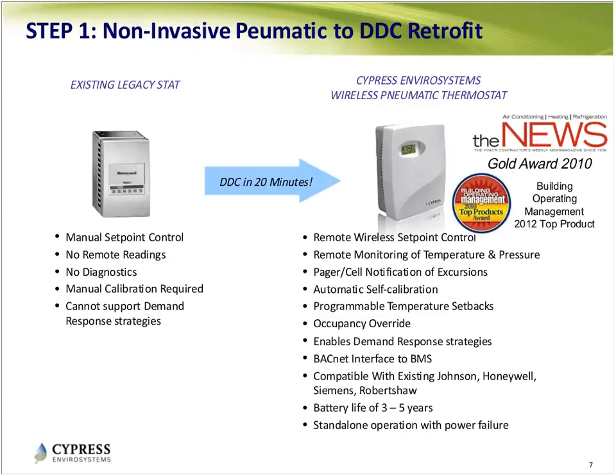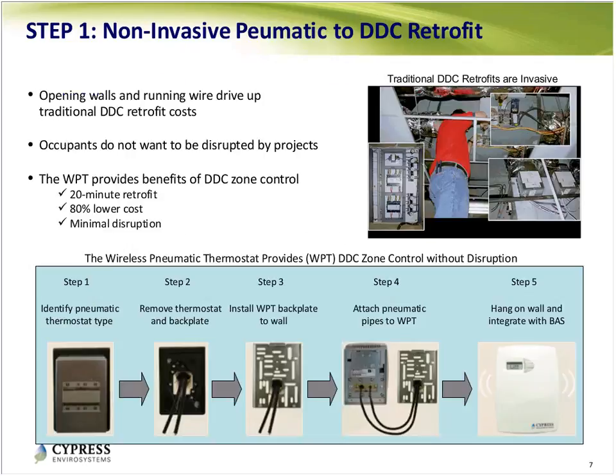Let me talk about the first step—how you upgrade your existing pneumatic thermostats. You pull the existing thermostat off the wall, and with this system, you don't have to open up walls and ceilings. You just take the old one off, connect the tubes back, and mount the new one on the wall. I have a picture of this here.